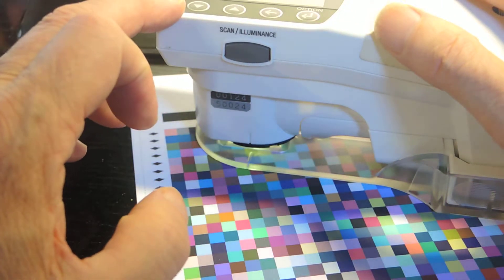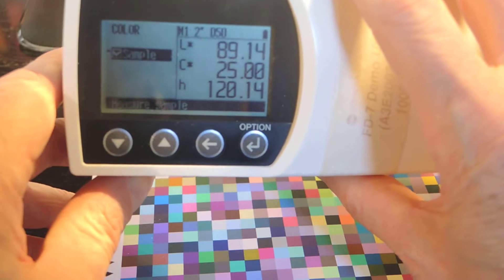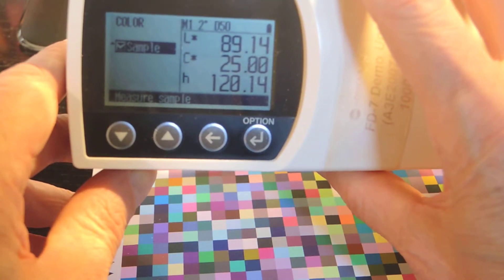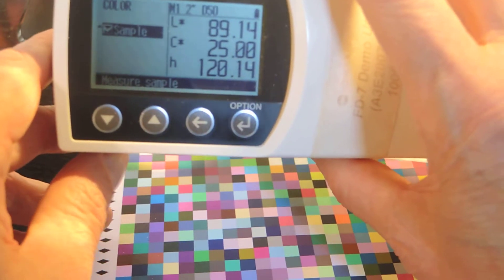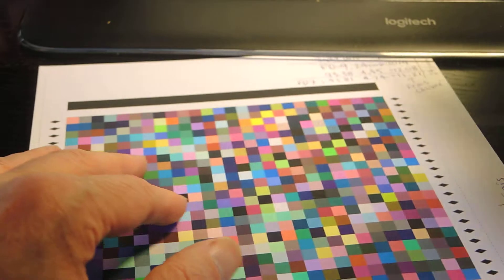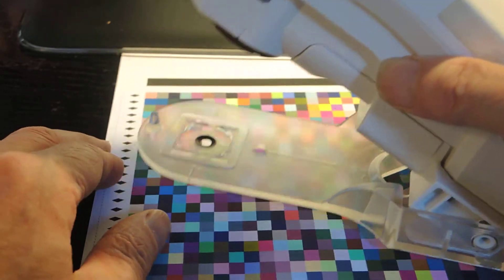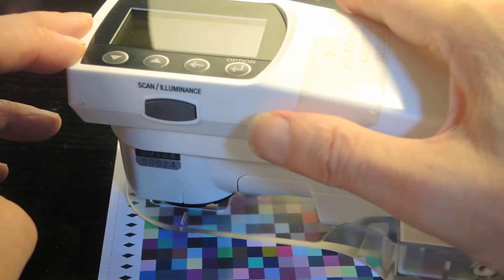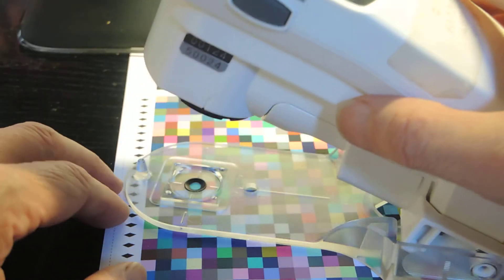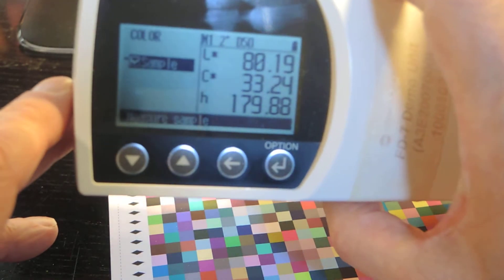So now if I measure any color, for instance, this yellow, which has a high chroma, so I get 89, 25, and 120 degrees for the hue angle. So 120 degrees, that's past 90 degrees. So it's a green, it's a yellow on, it's a green shade yellow. So if I press, if I measure this green color over here, this should be a little bit more. Aha, I knew it. See, 179 degrees.